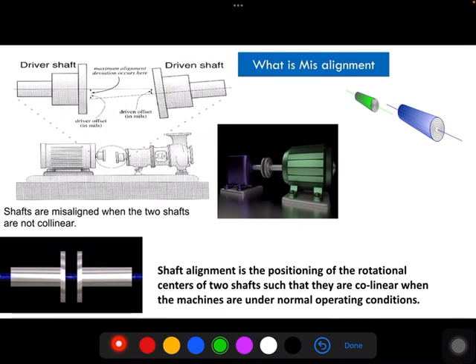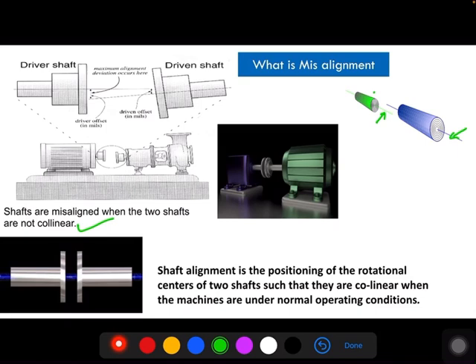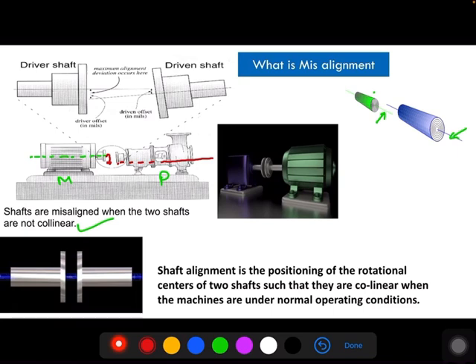Before going to spectrum and time waveform, first we will study what is misalignment, what is the effect, and what is the reason for misalignment. For any shaft, there is an axis called the rotational axis, and these shafts rotate about this rotational axis. When these rotational axes are not collinear, then it is called a misalignment condition. For example, consider a motor and a pump — if the axis of the motor and the axis of the pump are not collinear, then the machines are in a misaligned condition.